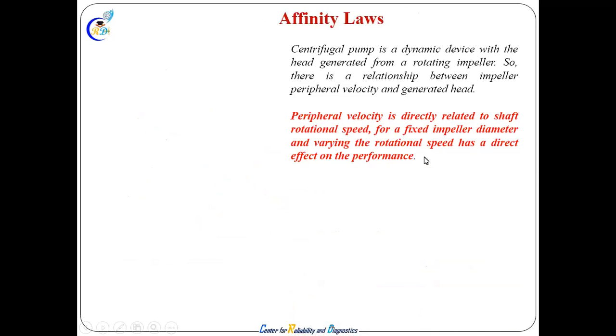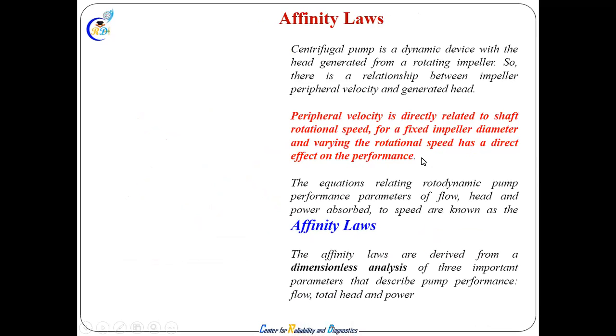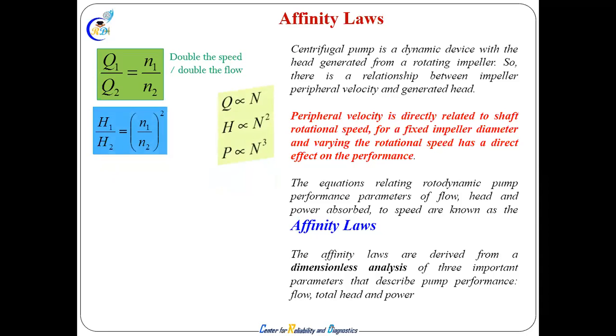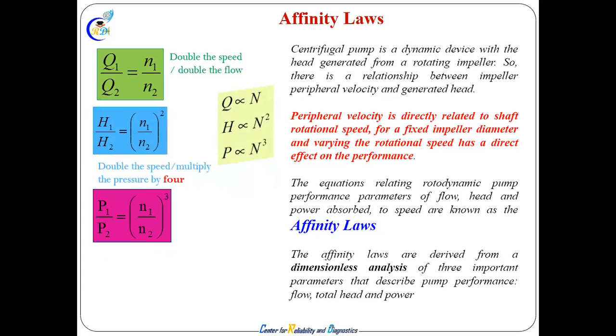So in the affinity laws, it is all about how much affinity there is between the parameters. In the affinity law, we are trying to explain at the unit level what our flow, head, and power requirement will be when you change the RPM. So whatever you think of in the VFD, you cannot do whatever you feel like. This is controlled by this formula. RPM can be changed. This is the way: a little RPM change, and your power requirement changes by a large factor.